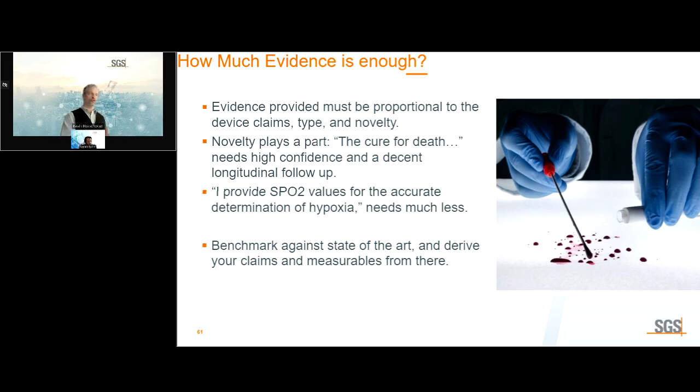So you have to do a literature search or in some way gather data that is repeatable and measurable for what the market looks like for other devices that are like yours or in the same space as yours. Then you have to prove to me that you meet those same as good or better. And if you want to get mathematical, not inferior or not non-inferior.